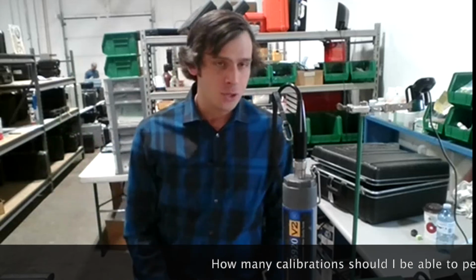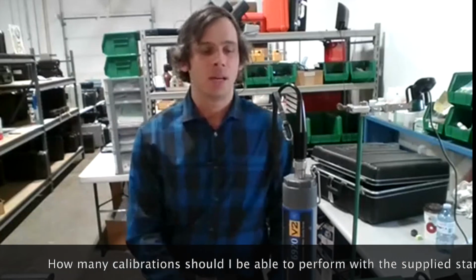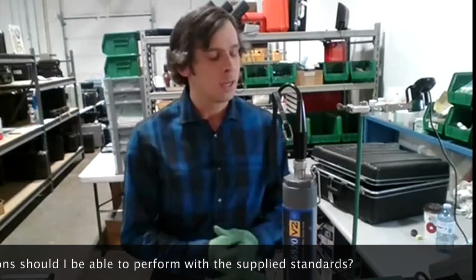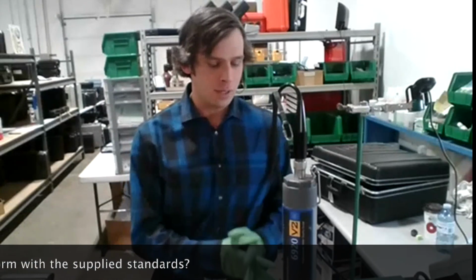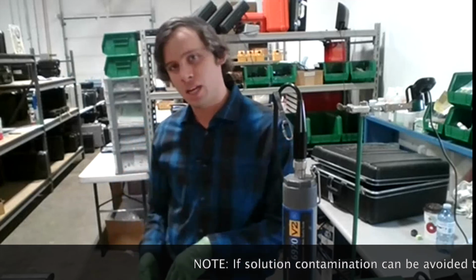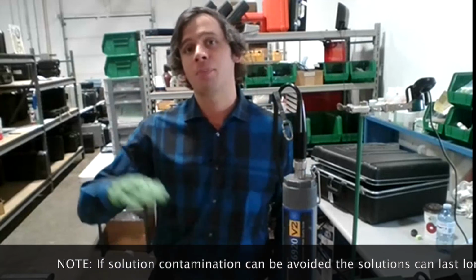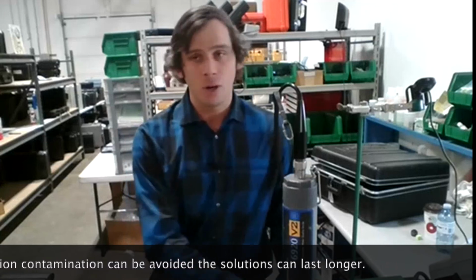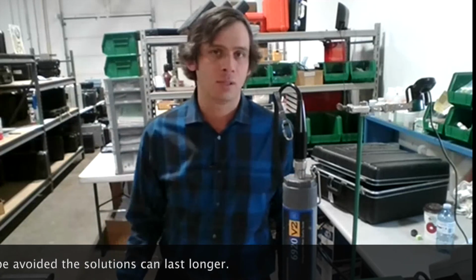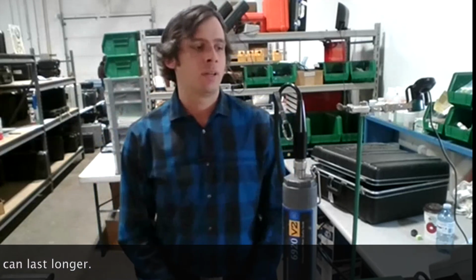The calibration solution, by my standards and what's highly advised, especially the turbidity solutions, should only be used once. As far as the other solutions, it really comes down to how well you take care of your sonde. It's really easy to cross-contaminate if you aren't cleaning the sonde in between your calibration steps. That would involve using DI water to make sure it's not only clean of the previous solution, but also dry so you don't dilute your next solution. So the 3 pH solutions would be as good as up to 3 calibrations, depending on how well you take care of it. Now, we always have more solutions here. We sell by 500 milliliters to jugs. We also have deionized water, so I highly recommend that if you are doing long-term and unattended sampling, every 2 to 4 weeks, it wouldn't hurt to either calibrate it, bump check it, or clean the unit.